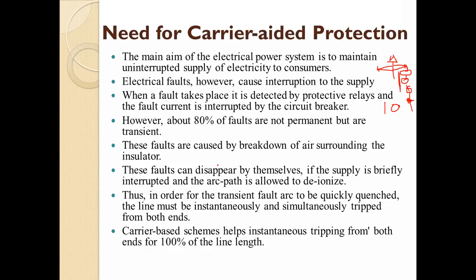Okay, and that if the supply is not continuous there after occurrence of fault, then what will happen? Now, there will be deionization. Okay, deionization means what? That arc get extinguished. Okay, म्हणजे ती जी आर्क आहे ती हळूहळू कमी होते. ओके, हळूहळू कमी होते. So in order for the transient fault arc to be quickly quenched, the line must be instantaneously and simultaneously tripped from both the ends.